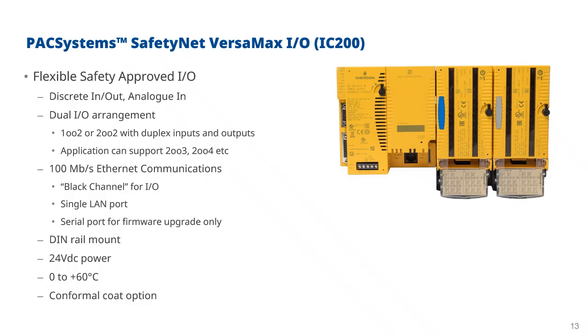On the I/O module side, we've got a combination of different modules. We've got a 32 channel discrete in, a 32 channel discrete out, and a 15 channel analog in. Analog outputs are not supported. If you wanted to use a system with analog outputs, then that would have to be in a separate non-safety system that could communicate via the main safety system with EGD. It's a dual I/O arrangement. You do need 2 lots of inputs and outputs, so the complete I/O stack would be duplicated.